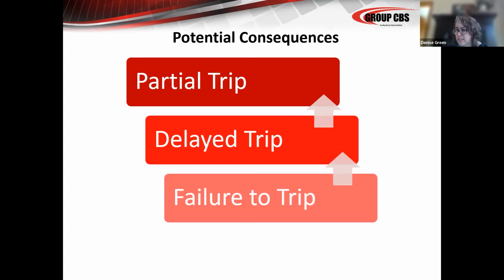Okay, some consequences that can happen with a lack of maintenance on a breaker. And the two bottom ones are pretty close in the severity. So it was kind of a toss up on which to put first. But I'm going to start at the bottom. So our first problem that happens with a breaker that hasn't been maintained is that it doesn't trip as expected. So it gets a signal, whatever trip unit is on the breaker sends the proper signal, whether it's a solid state trip unit from the CTs to the actuator, whether it's an electromechanical trip unit, whether it's a thermomagnetic trip unit in a molded case breaker.